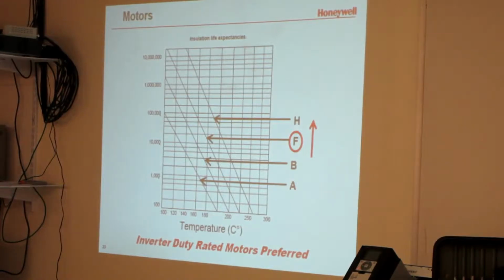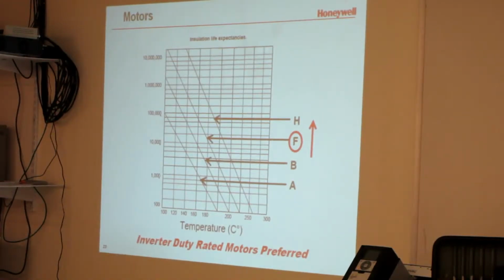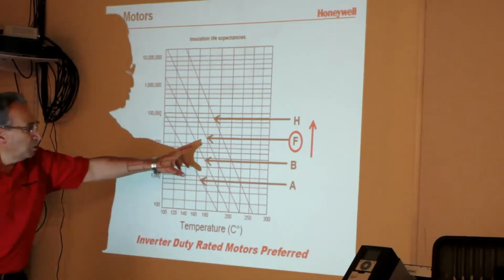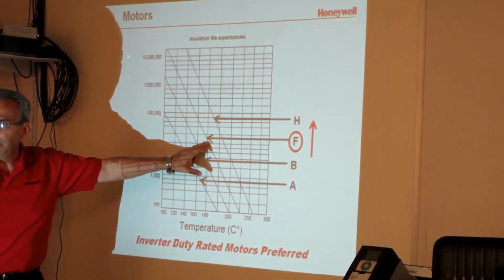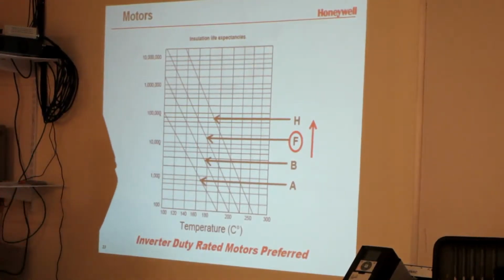Because a drive puts heat on that motor. The low frequency harmonics start heating that motor. And so you want insulation on the motor that'll handle that. Now, most of the newer motors are pretty well insulated. The older motors, you might have run into ones that didn't have a good class of insulation. But I think most, if not all the motors, insulation is not the issue.